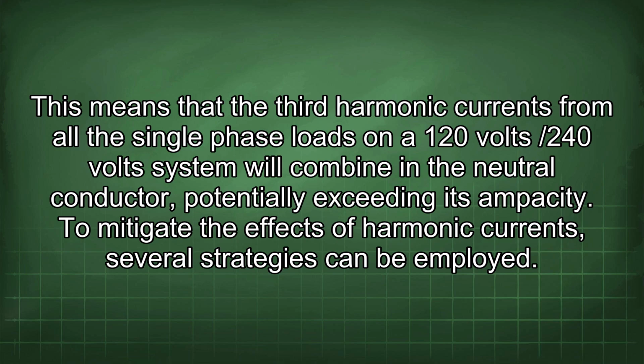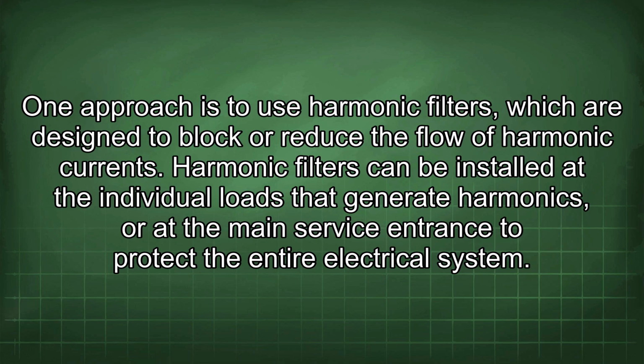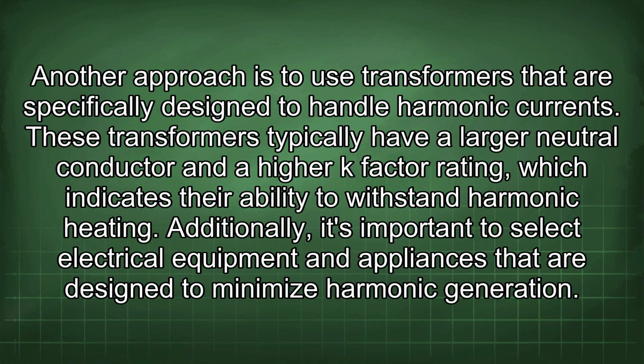To mitigate the effects of harmonic currents, several strategies can be employed. One approach is to use harmonic filters, which are designed to block or reduce the flow of harmonic currents. Harmonic filters can be installed at the individual loads that generate harmonics, or at the main service entrance to protect the entire electrical system. Another approach is to use transformers that are specifically designed to handle harmonic currents. These transformers typically have a larger neutral conductor and a higher K-factor rating, which indicates their ability to withstand harmonic heating.